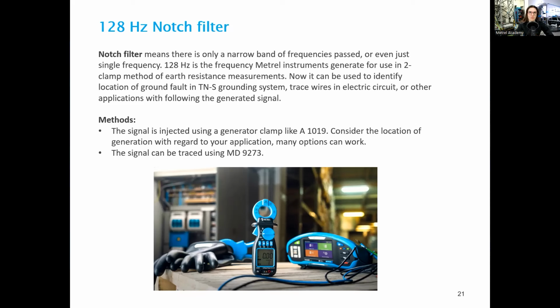As we're going to take a look, it will enable us to look for installation problems while our installation is in operation. Now, if we look at what a notch filter means and how it works. A notch filter is a filter that only lets through a very narrow band of frequencies, or even only a single frequency.